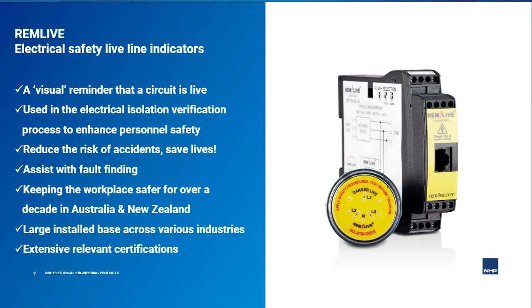The idea for REMLIVE warning indicators came after a fatal incident at a steelworks in Wales back in the late 1990s. We've worked with our partners and customers ever since to provide a simple and reliable way to show that an electrical circuit is live. REMLIVE liveline indicators provide that visual reminder to an operator or user that the circuit is live and can be used to observe the change in state when our LEDs on the display go from on to off. And that's when the isolator device is typically switched to off.